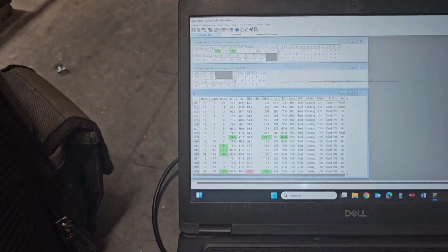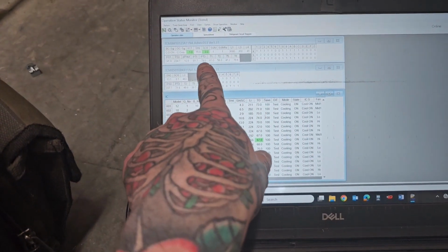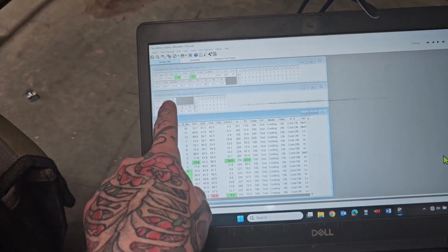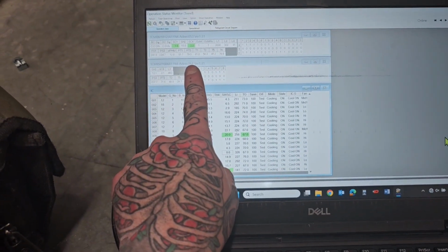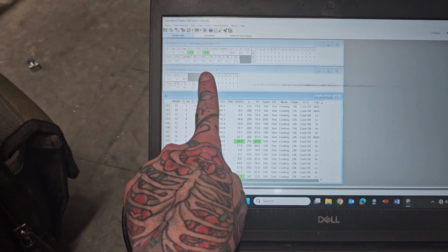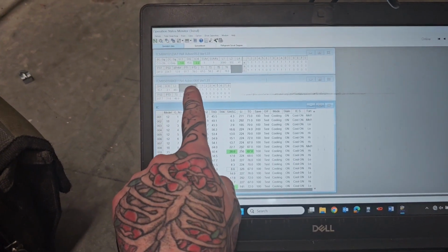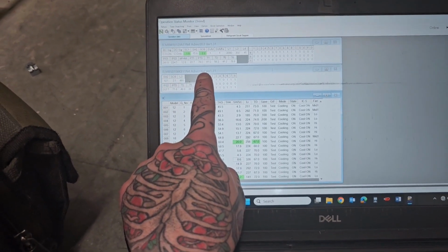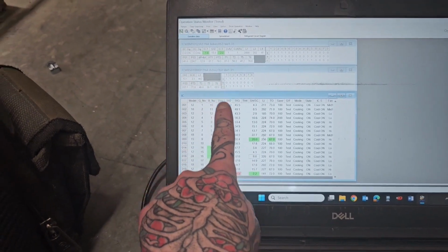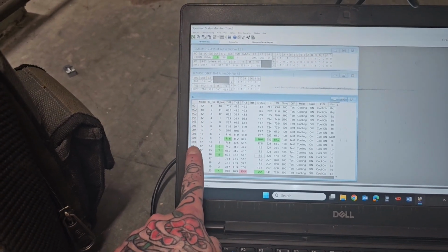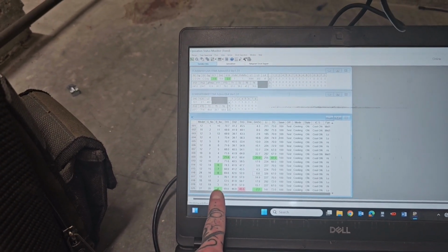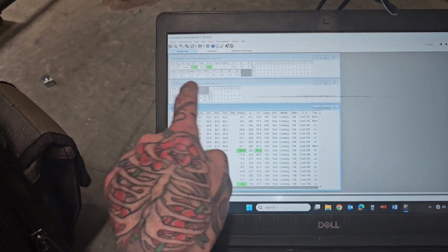They have to be 50 higher than the lowest addressed unit that is connected to them. In this case, it's address 64. So that tells the sub branch controller, hey, you are connected on 14 and up. So everything including 14 and up is connected to you.